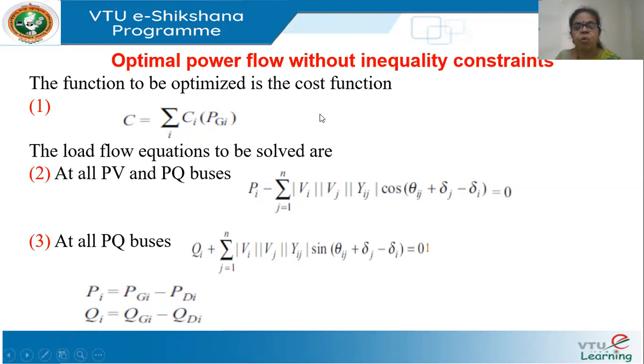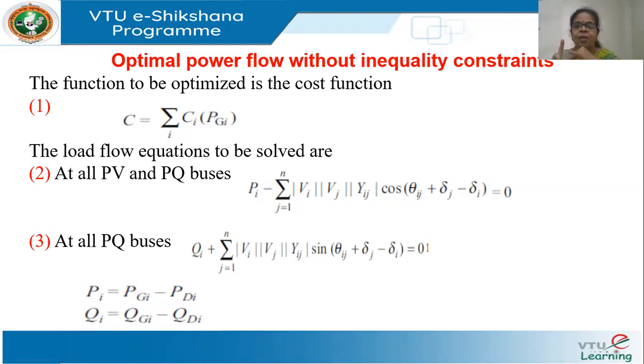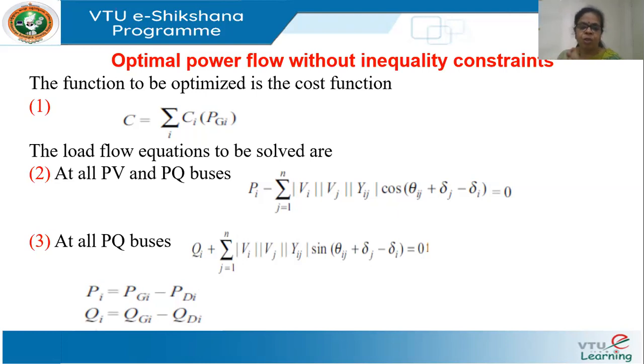For example, the voltage should lie between the minimum and maximum, the power generation of each plant should be within Pg_min and Pg_max, the Q limits, and so on. Those are the inequality constraints. First, let us understand the optimal power flow problem when we don't have inequality constraints. The function to be optimized is the cost function C, which is Ci as a function of Pg — how much generation there is.